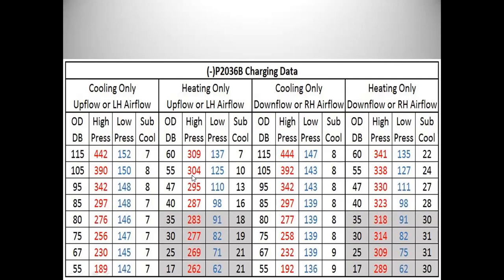But just for safe here, if we go to 47 degrees in heating on an upflow, our pressures will be somewhere around 295 and 110, and a subcooling of 13. Actually, you know what? Hold on, this is a different chart here. So let me go over, yeah, that's it. So we'll go over here to the downflow heating. So 47 degrees here. If we follow this over, the 330 is not too far off from the 295. The suction pressure is 111, not terribly far off from your upflow, but you'll notice your subcooling is wildly different. In a downflow position, the required subcooling is 27, and in upflow it's 13.